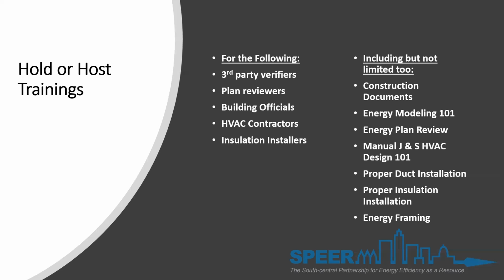That includes making sure manual J, manual S, and HVAC design are done correctly. And then from an inspector standpoint, proper duct installation - have trainings on that. What does it look like in the field? Walk a site and say this looks good or this doesn't, here's what needs to be done. There are ACCA and ASHRAE documents or brochures out there that show best practices for duct installation. I train on that quite a bit, and of course proper installation.